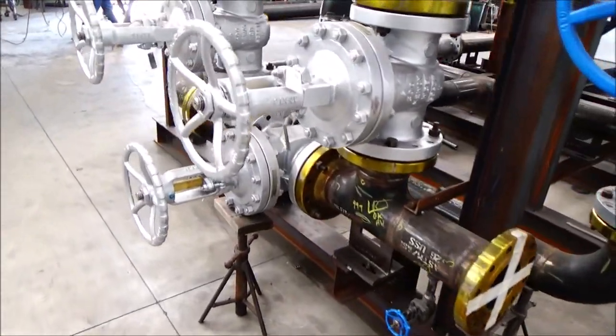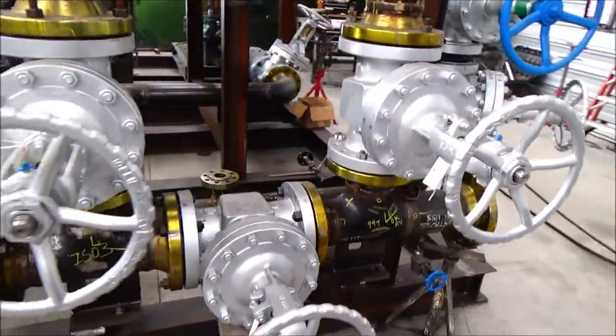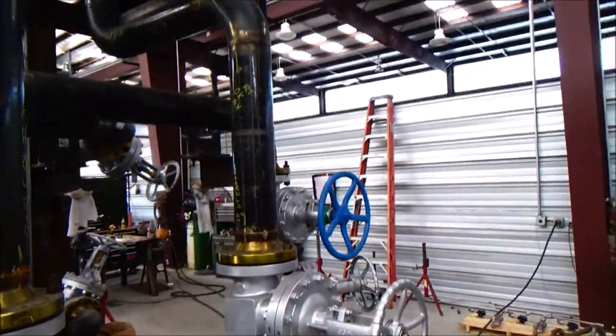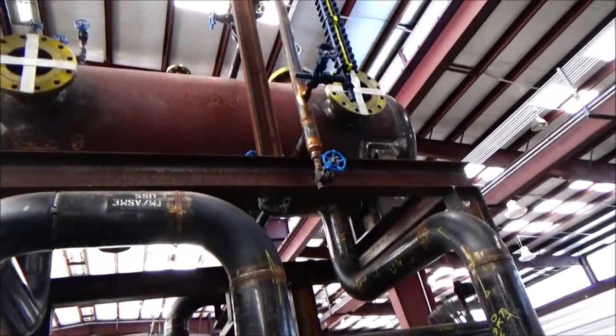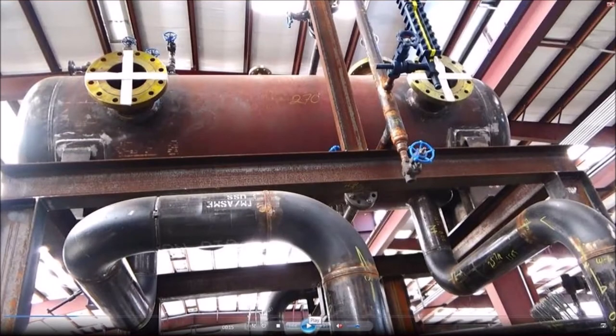Hot oil enters the system through a double block and bleed using high temperature gate valves. The expansion tank is sized for one third full cold and two thirds full hot. The oil will go through the expansion tank until it is settled.